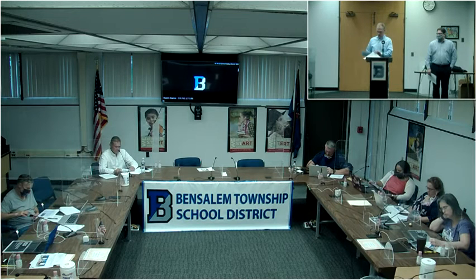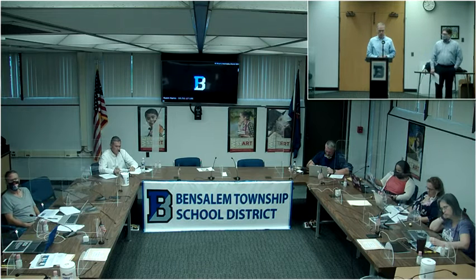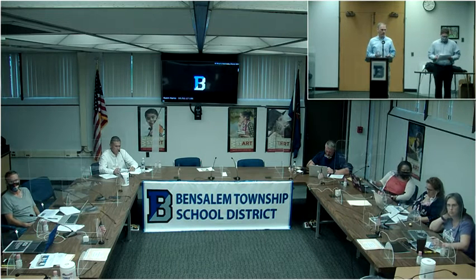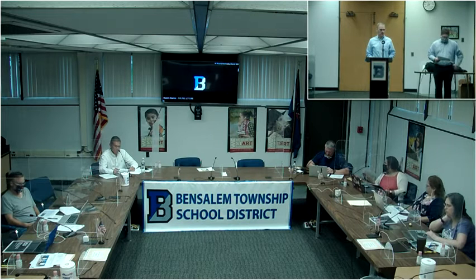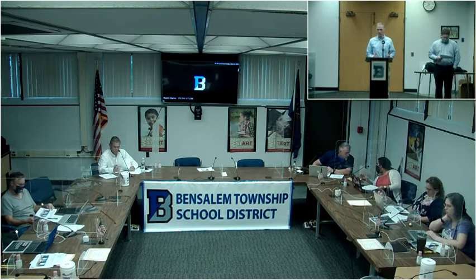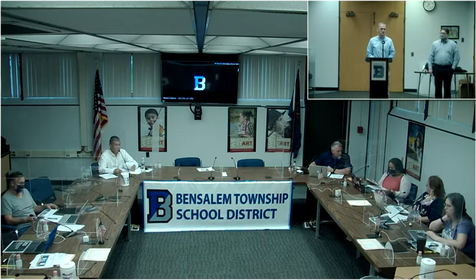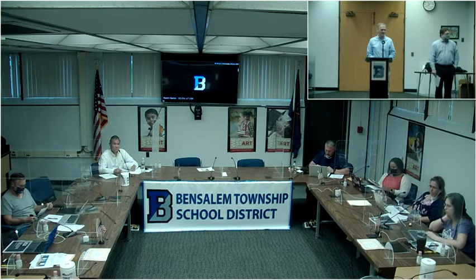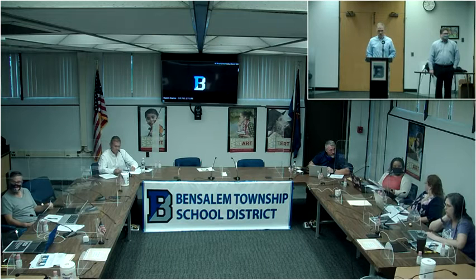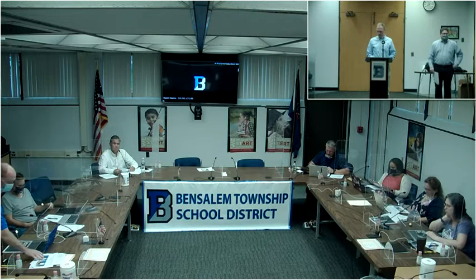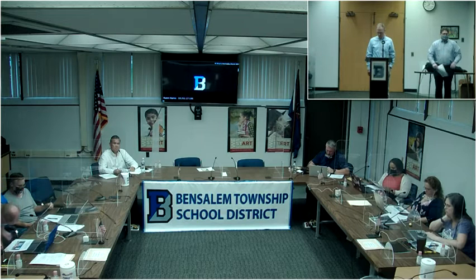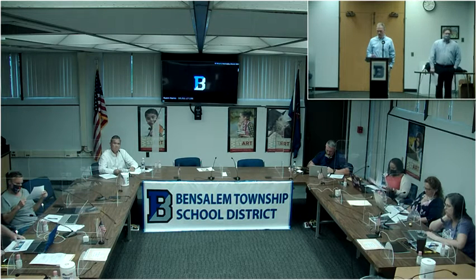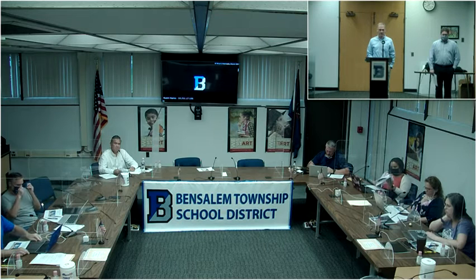The second page shows what we refer to as replacement units for the base proposal. One key thing you look for with any replacement units is avoiding the water infiltration you're dealing with now. You may have noticed on the first page some gutters on rooftop units with what looks like downspout material — that's not something we normally see on HVAC equipment on roofs. With any manufacturer, such as Carrier, which was mentioned as a district preference, we'd specify unit construction that wouldn't have that issue.